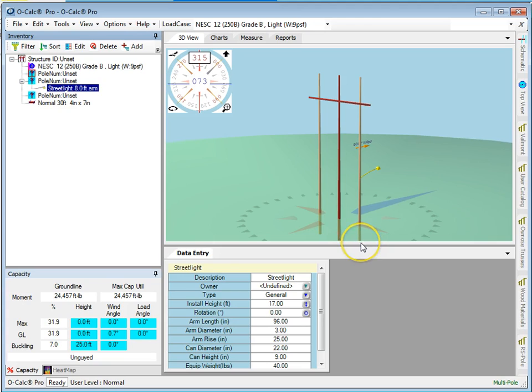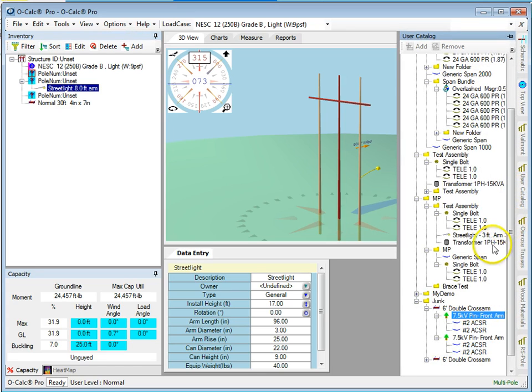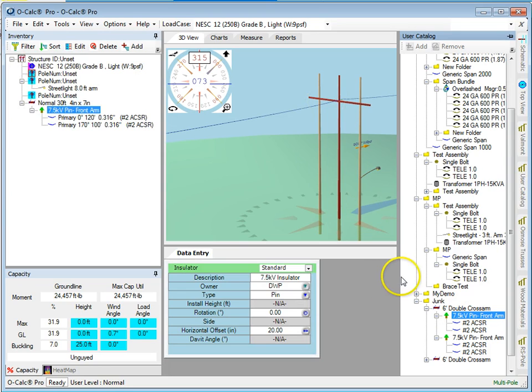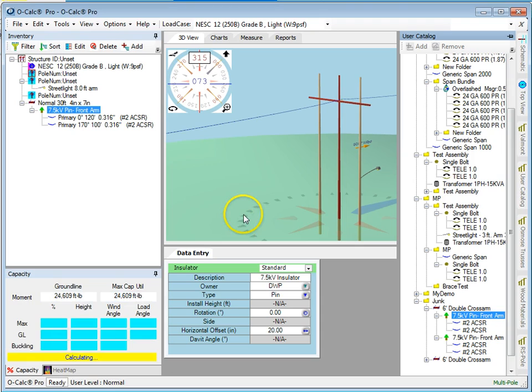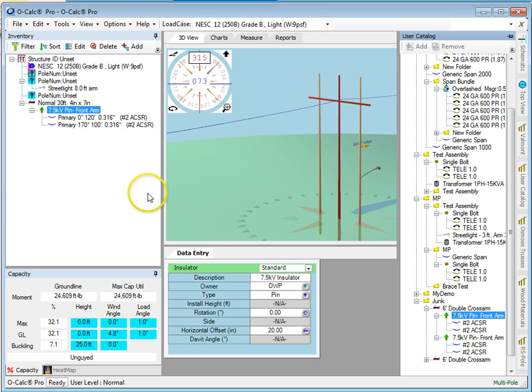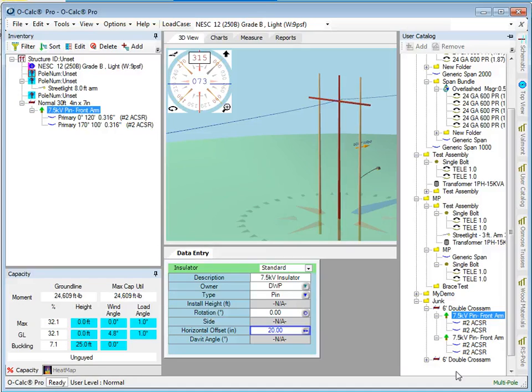So let's go ahead and put our loads on there. I'm going to put my user catalog just to make things a little bit easier. And I will take and I'll put this prebuilt insulator and two spans on here. Now, typically because these are meant to go on smaller cross arms, you'll see that the units in the offset value, the distance from the centroid of the cross arm that the insulator is placed, is 20 inches.